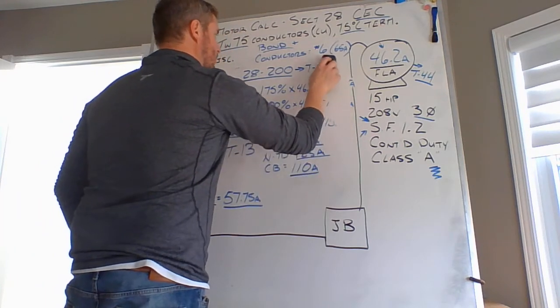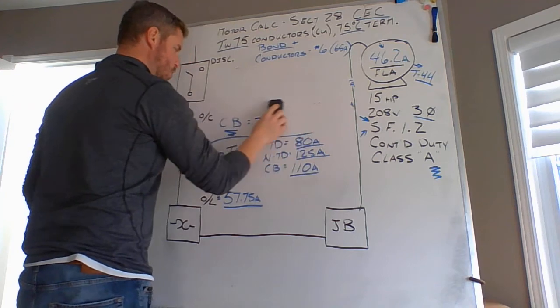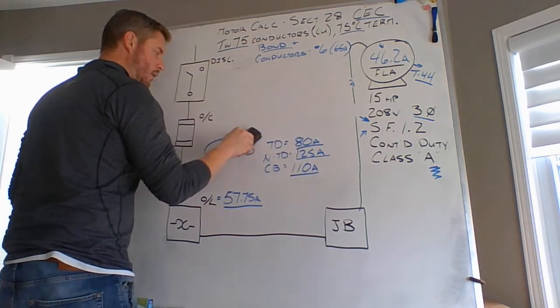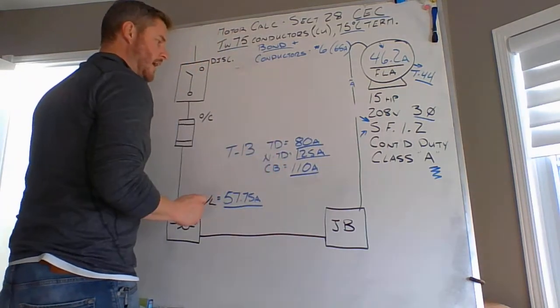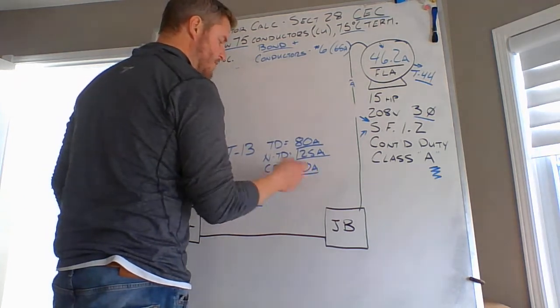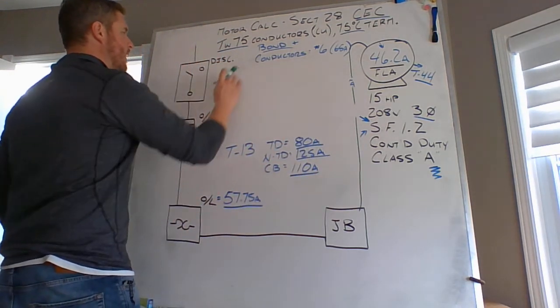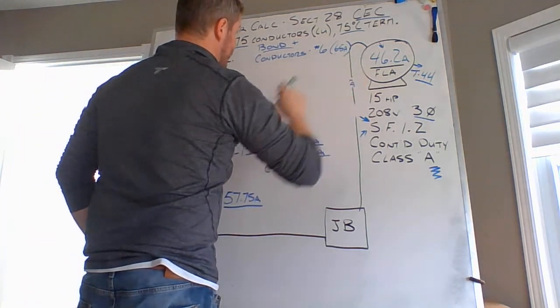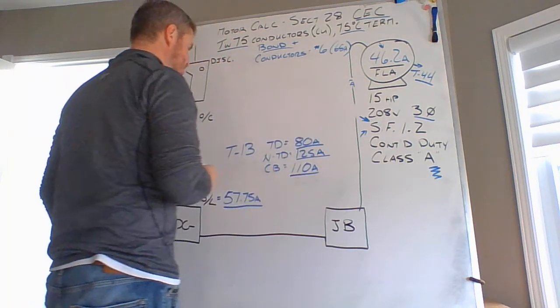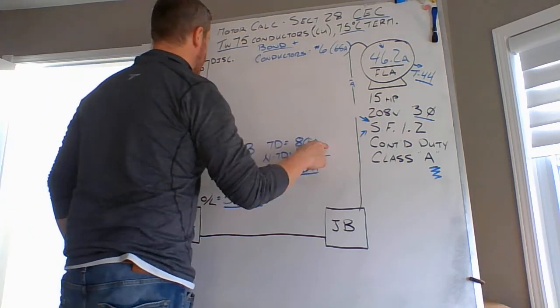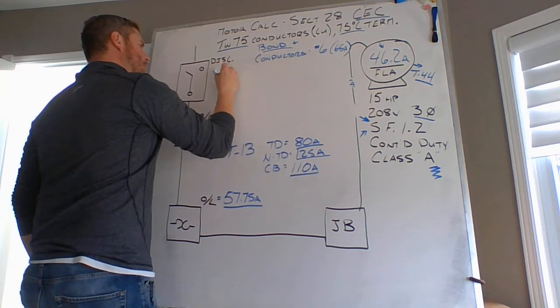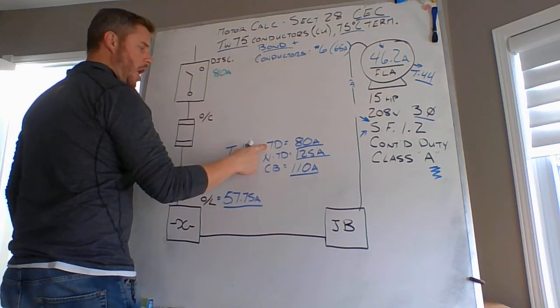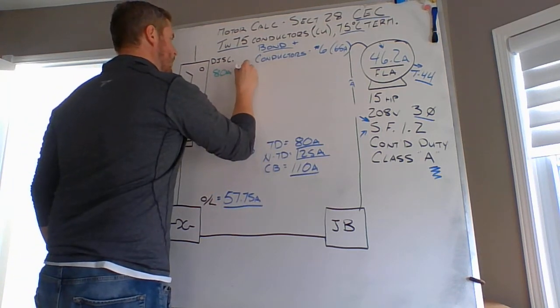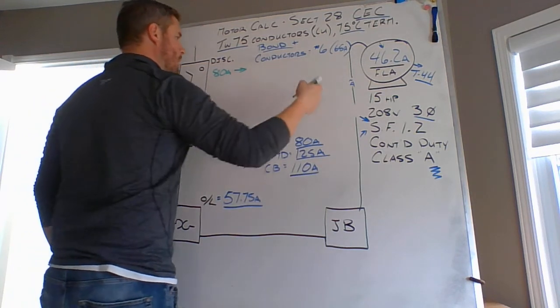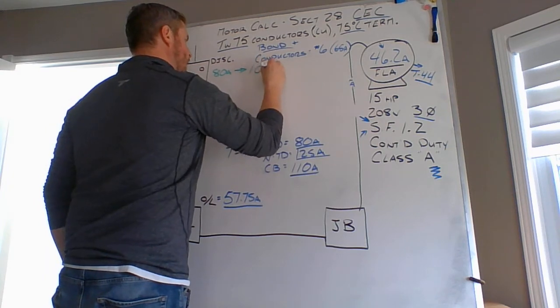But we have to accommodate for that. So herein lies the problem. Here's the issue. And here's how you have to start thinking towards the future. These are your installed values down here. I'm getting rid of your calculated values because you should have that recorded already. Here's what happens when you try to install an 80 amp fuse or a 125 amp non-time delay fuse or a 110 amp circuit breaker. The circuit breaker, not such a big thing. All right, this motor, 46.2 amps, better never draw more than 46.2 amps. So if I took my time delay fuse operation, that would mean that I'm installing 80 amp fuses into a disconnect as a time delay operation. At that point in time, I know that I'm installing 80 amp fuses for the overcurrent protection of this motor. That means that they're going to go into a minimum 100 amp disconnect.